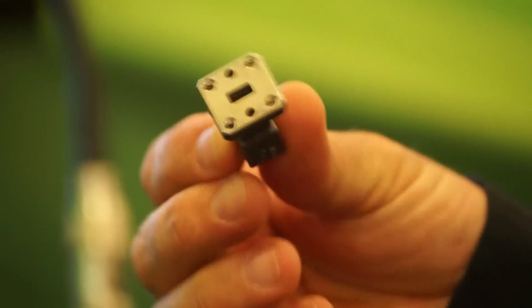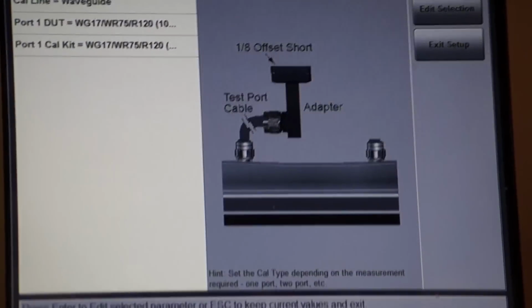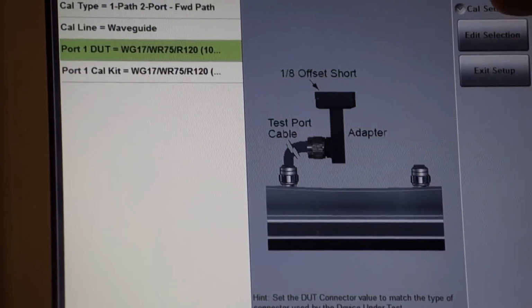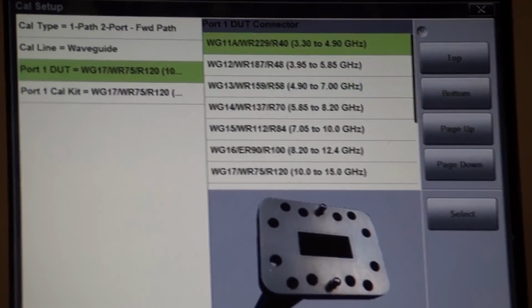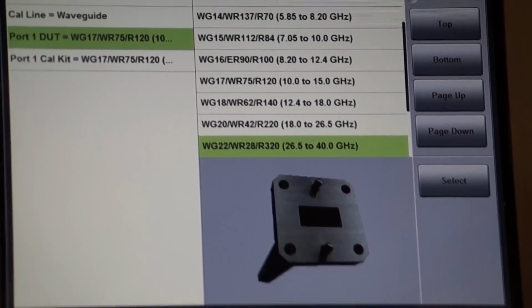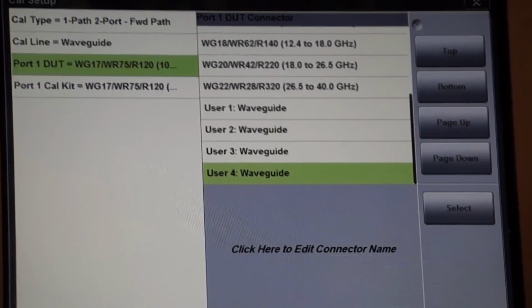Because of its wide frequency range, it is also able to handle waveguide components. This is a 26.5 to 40 gigahertz waveguide component, and measuring waveguide components with this instrument is as easy as going into the calibration menu and selecting the waveguide type that you want to use. Down here you would select the waveguide type. We have 10 bands built in, and then we offer the user the ability to add 4 of their own custom bands in case they have waveguide types that aren't one of these 10 that we've provided.